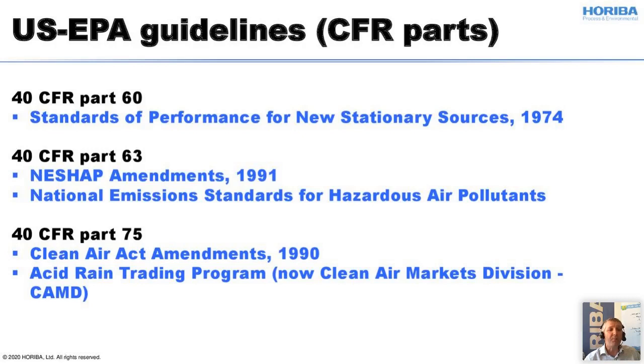In the US, we have EPA guidelines. This is the Code of Federal Regulations. This is 40 CFR Part 60, 40 CFR 63, and 40 CFR 75. All three regulations can be, but not directly, compared with the European regulation. All of them are a kind of standard of performance. Then you have emission standards for hazardous air pollutants and the acid rain trading program. The difference between the EU and the US EPA guidelines is that the US EPA only has EPA compliant instruments or systems. The EU directives and standards are requesting certified systems. On these certification requests, I will go into more detail in the next slides.